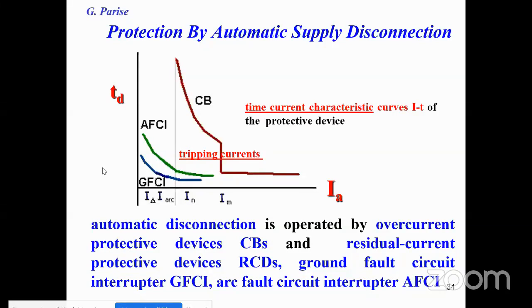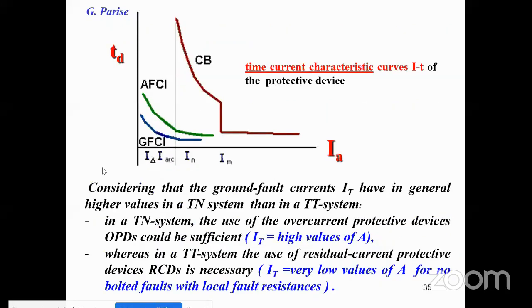It is very important to use for low values of the fault current. Arc fault circuit interrupters are particular protective devices for the arc fault. Considering that the ground fault currents have, in general, higher values in a TN-S system than in a TT system, in a TN-S system the use of overcurrent protective devices could be sufficient, because the current in the slide we show is 1,500 amps. An overcurrent protective device can protect against a ground fault.